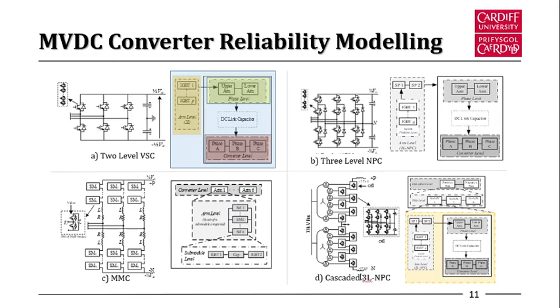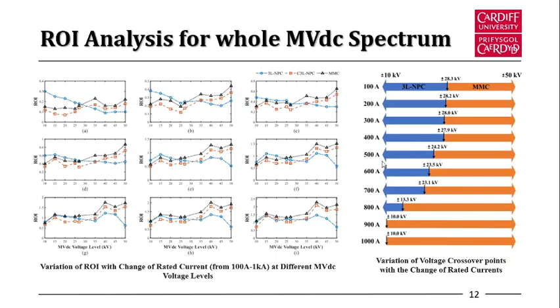The analysis has been performed at various currents and medium voltage DC levels, starting from 10 kilovolts to 50 kilovolts, with a current range of 100 amperes to 1 kiloampere. These results show that with the increase of medium voltage DC level and current level, MMC is the more suitable topology, whereas at low MVDC and current levels, the 3-level NPC is more economical.